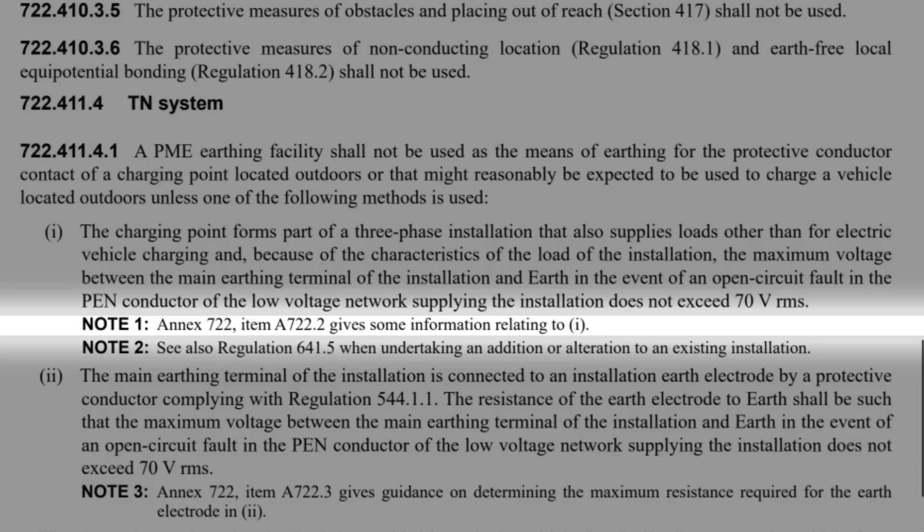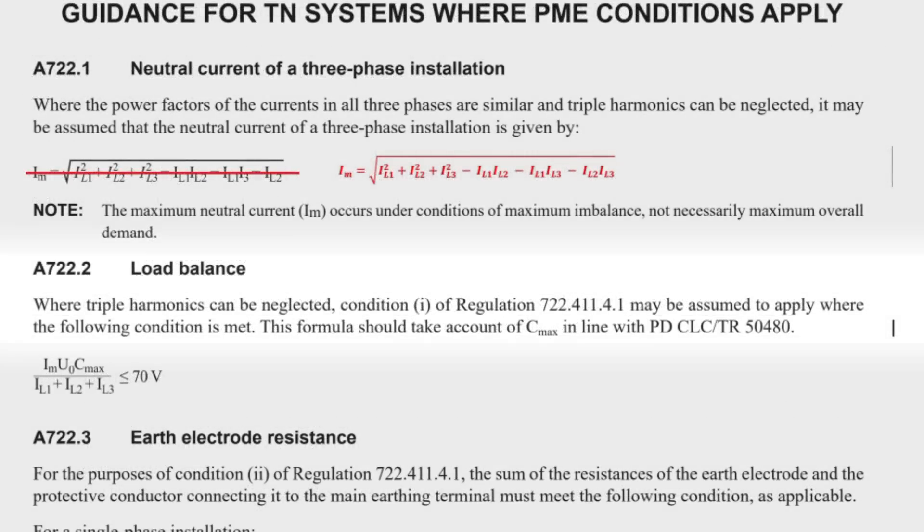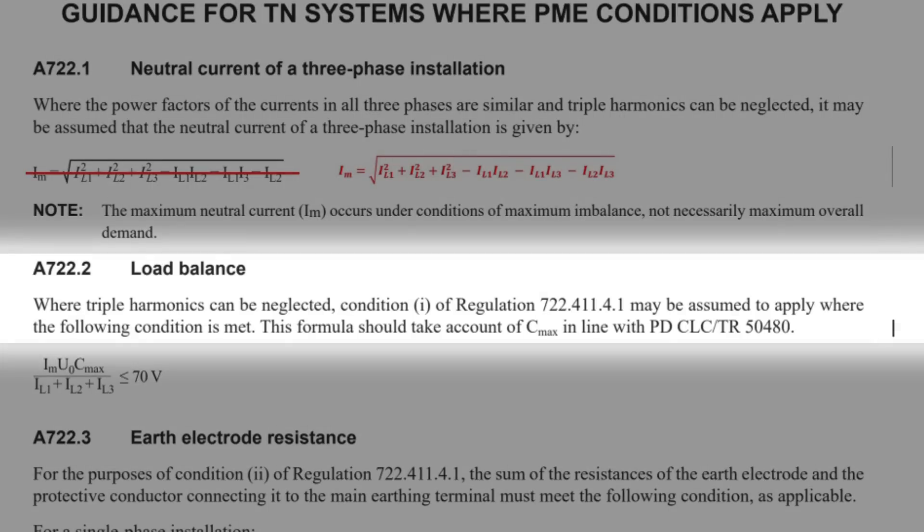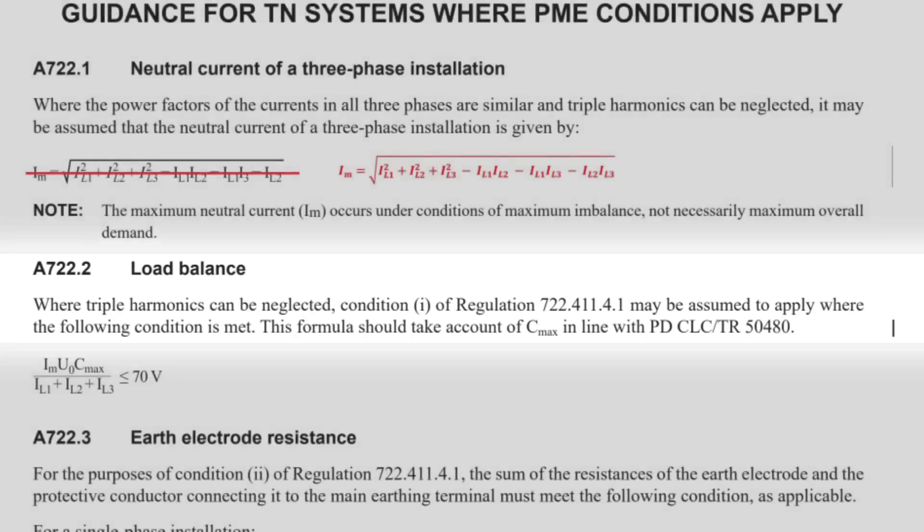Well note 1 to that indent tells us that Annex 722 item A722.2 gives some information relating to 1. So turning to that reference we find that where triple harmonics can be neglected, condition 1 of regulation 722.411.4.1, which is the reg we're reading at the moment, may be assumed to apply where the following condition is met. This formula should take account of Cmax in line with PD CLC TR 50480. There then follows a rather intimidating looking formula.